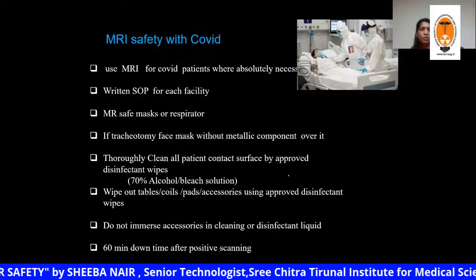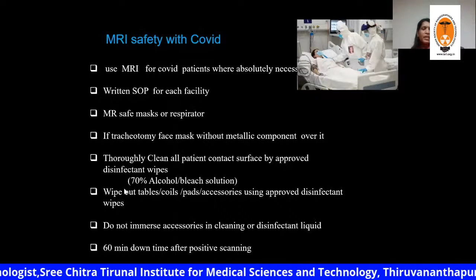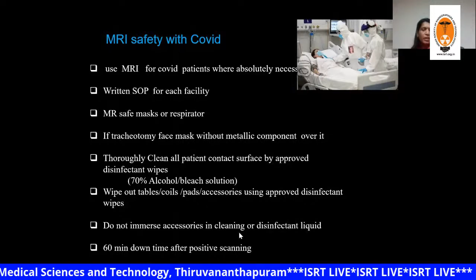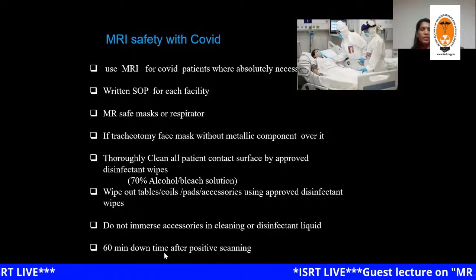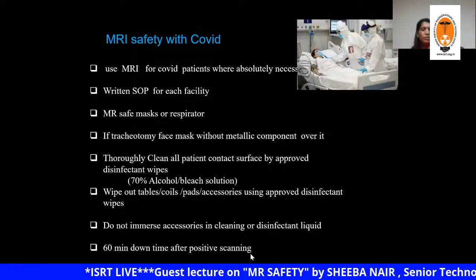Usually 70% alcohol or bleach solution can be used to clean the coils, tables, pads, and accessories. Everything should be wiped with a disinfectant wipe. Never immerse the accessories or coils in a cleaning or disinfectant liquid. If required after a positive patient scan, we can allow a downtime of 30 to 60 minutes. It is recommended that after an interval of 30 to 60 minutes, you can do the next scanning.